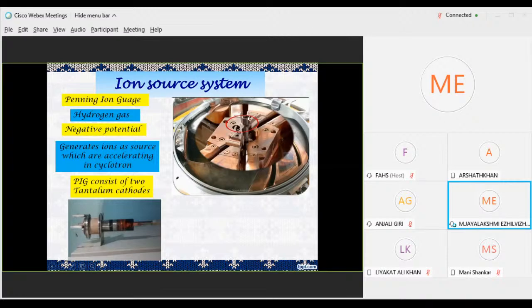It is filled with hydrogen gas, and it is at a negative potential. Through here, the ions are being born. They are newly born and they are accelerated throughout the entire cyclotron. So this generates ions as a source, and they accelerate in the cyclotron. This Penning ion gauge consists of two tantalum cathodes, as you see here in the picture.